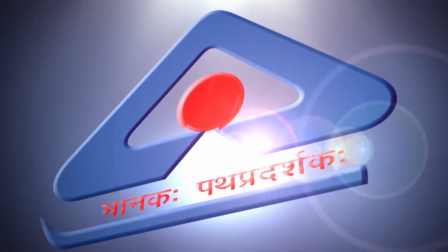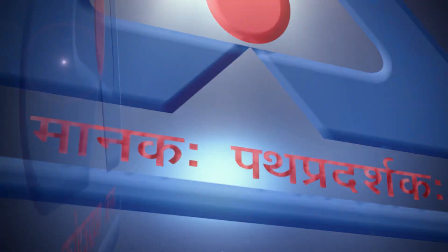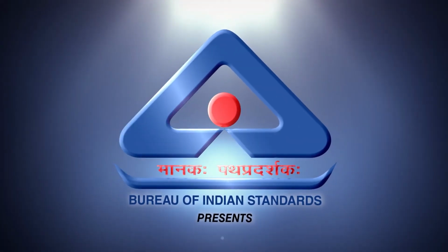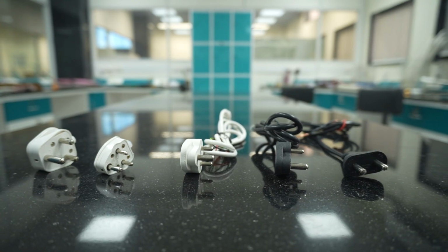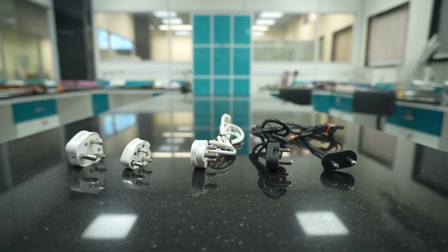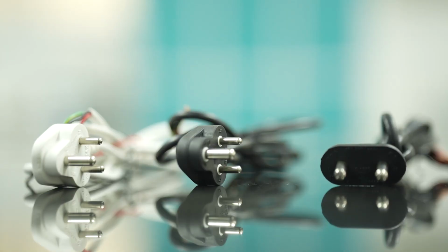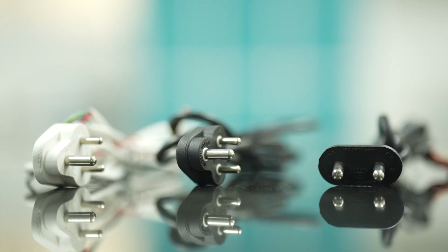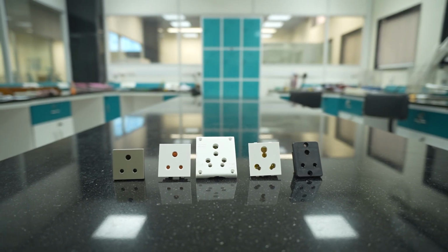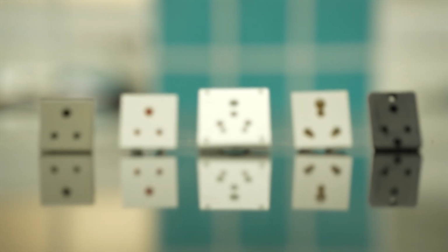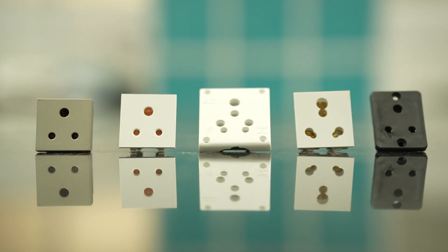The Bureau of Indian Standards has developed a standard, IS 1293-2019, which specifies the dimensions, specifications and requirements for plugs and socket outlets used in India. Here are the key definitions. Plugs: devices that are inserted into socket outlets to make an electrical connection. They typically have pins that fit into corresponding holes in the socket outlet. Socket outlets: devices that receive plugs to provide an electrical connection. They have holes or slots to accommodate the pins of the plug.